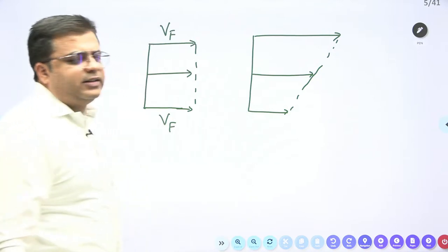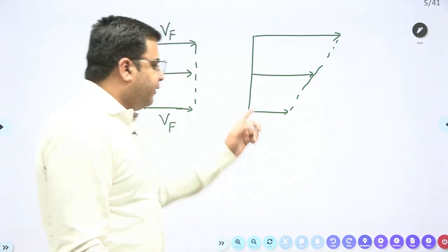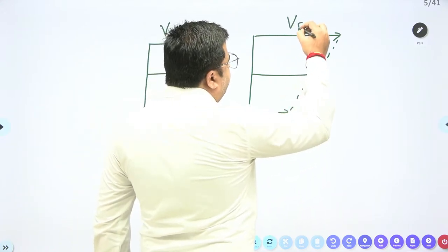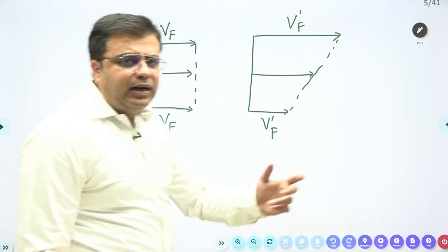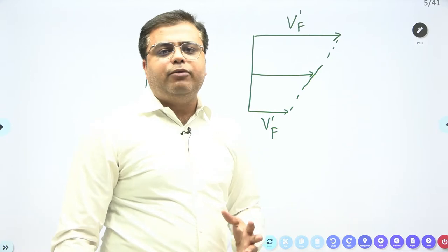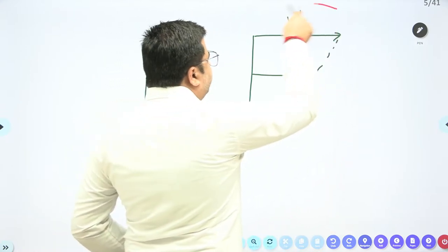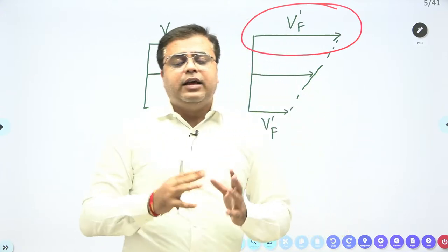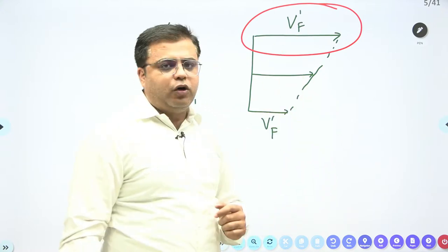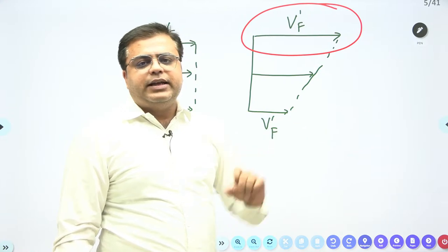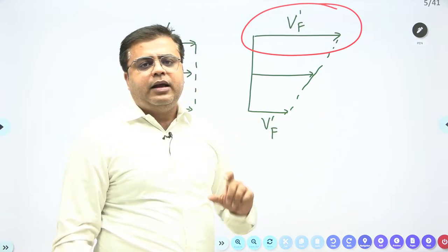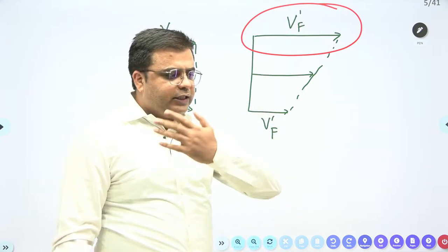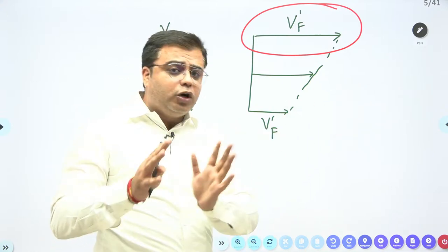Due to the frictional resistance offered by the surface of the tank, the velocity of flow at the bottom layer will be less, and the velocity of flow at the top layer will be more. Due to this, the practical detention time you have provided to the top layer will not be available, and the time required for the particles to settle will not be there due to the higher velocity of flow. The particles present in the upper layer will not get sufficient time to settle in the settling tank, right? Due to this, these particles which were supposed to settle will move out of the system.